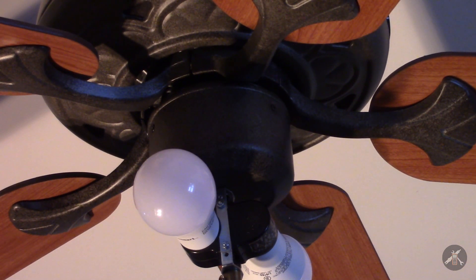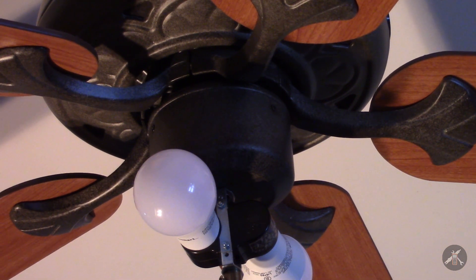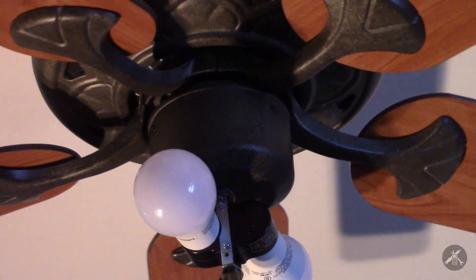But for my fan, the 6.5 microfarad cap seems like it's the right speed, so I'm going to leave that alone. And I'm going to try this again and see how it works. Seems like it works about right.